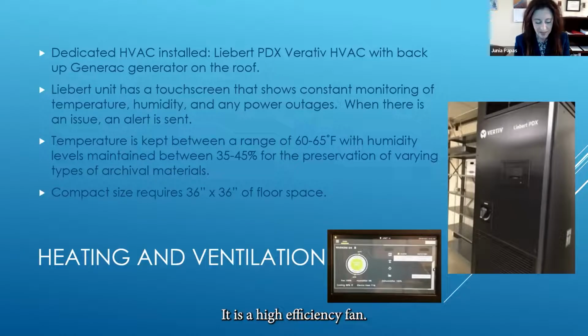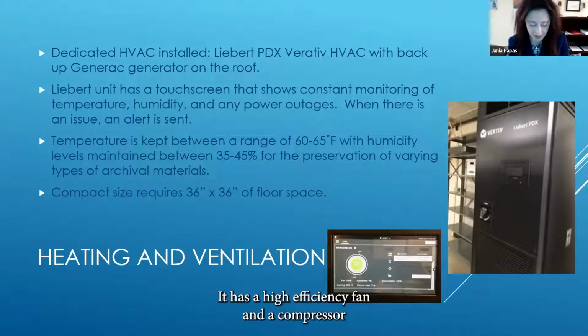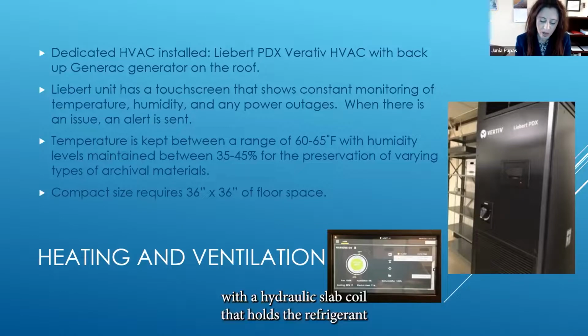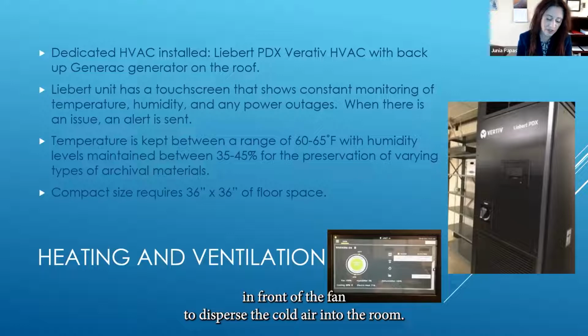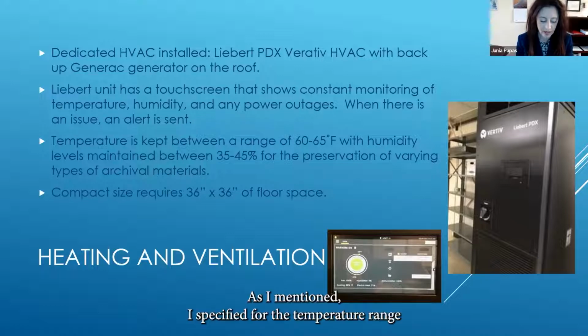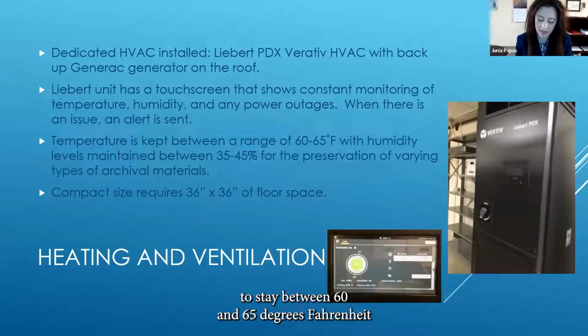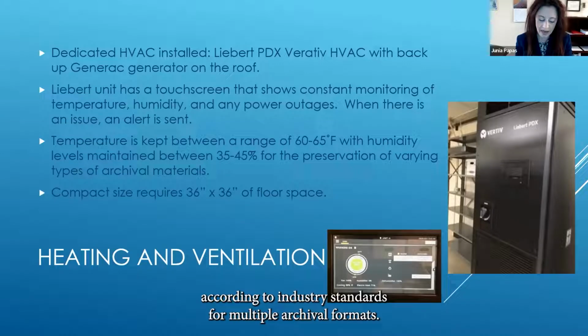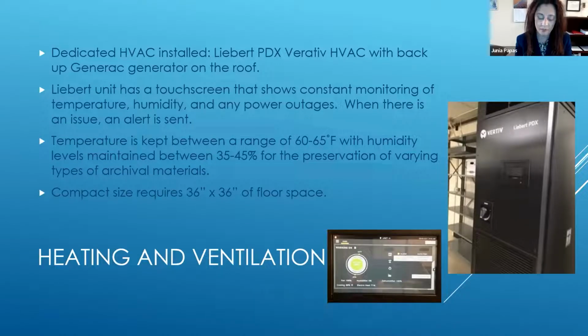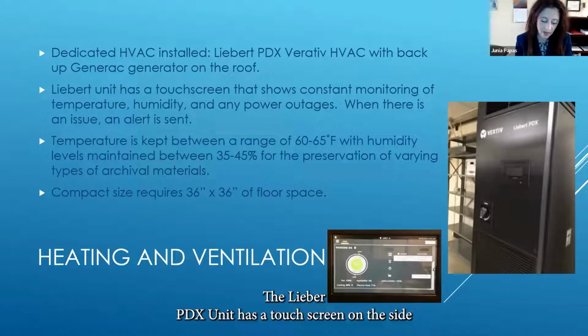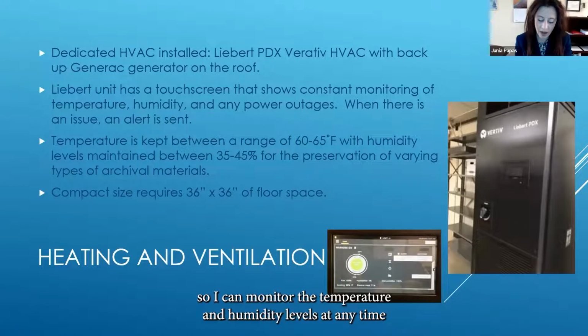It has a high efficiency fan and a compressor with a hydraulic slab coil that holds the refrigerant in front of the fan to disperse the cooled air into the room. As I mentioned, I specified for the temperature range to stay between 60 and 65 degrees Fahrenheit, and the humidity level to be between 35 and 45%, according to industry standards for multiple archival formats. The Liebert PDX unit has a touch screen on the side, so I can monitor the temperature and humidity levels at any time.